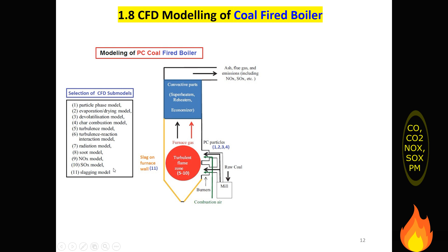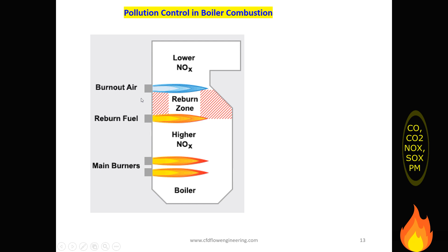For the boiler, what techniques are used to control the emission? Main burners are kept at the bottom, and some reburn fuel is kept at a higher level. That means there is fuel staging, and air is again supplied additionally to control the temperature of the flue gases. There is also a burnout zone. But this is just for illustration; as far as my experience is concerned, they use some burners at the bottom and some tertiary air is supplied at the top.